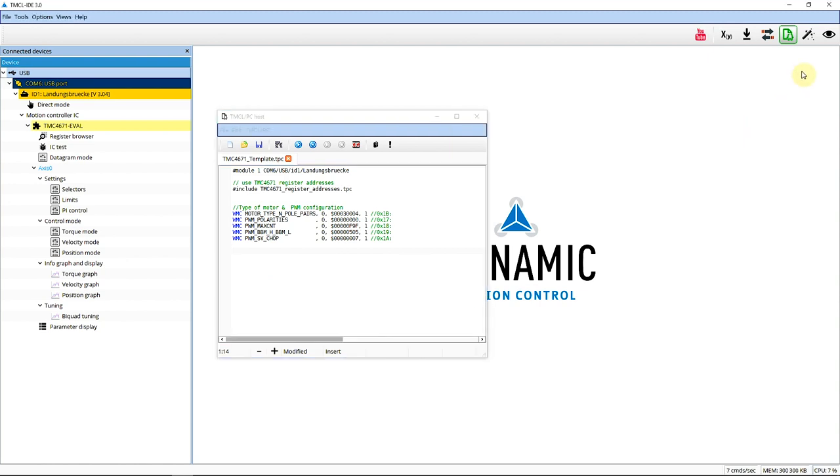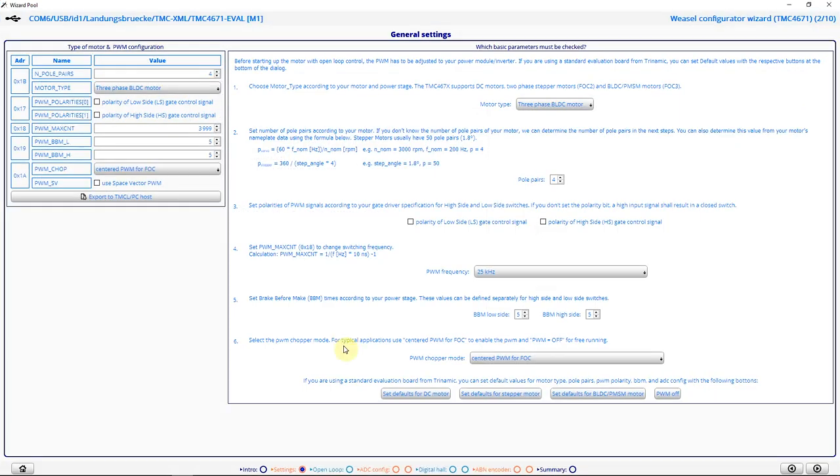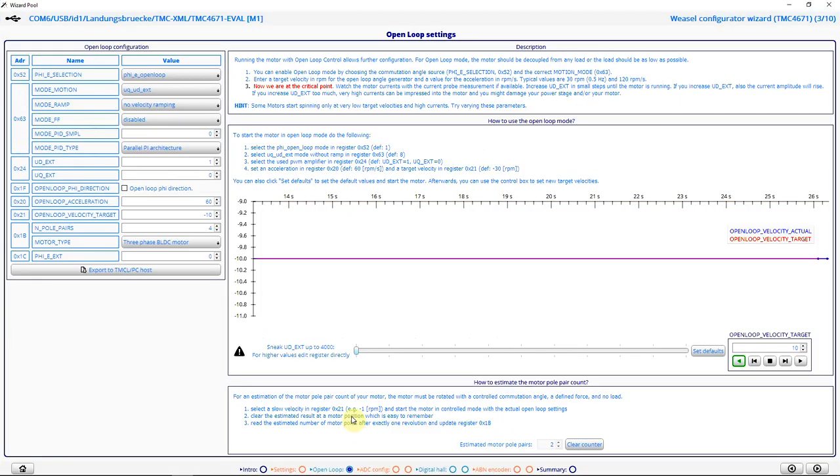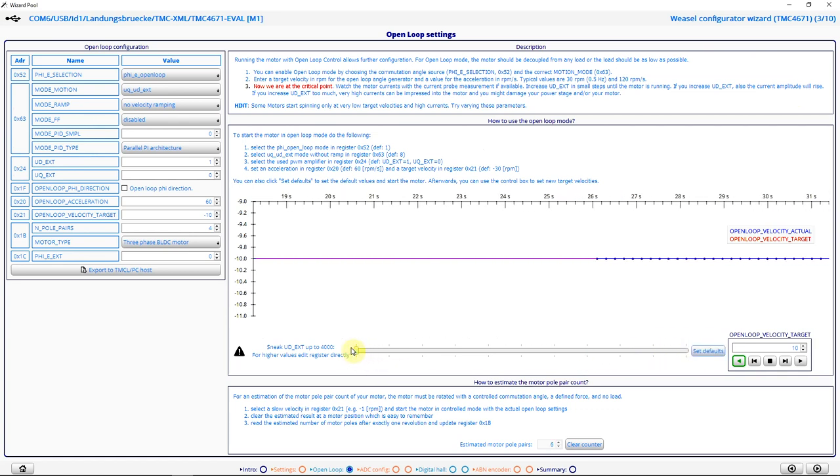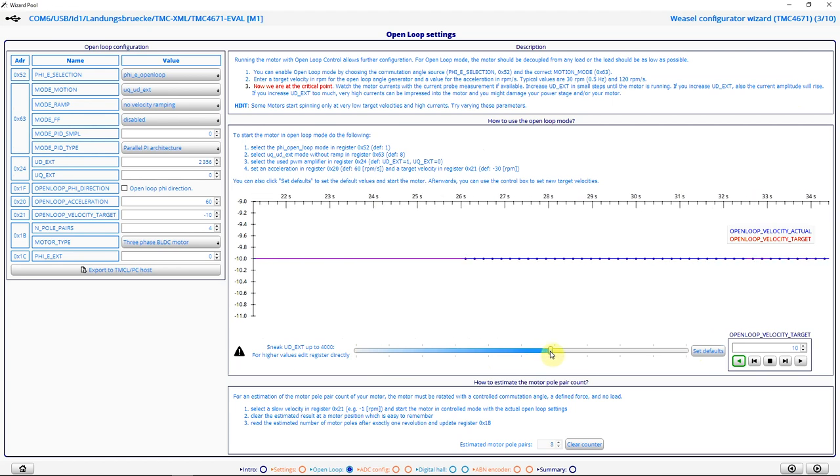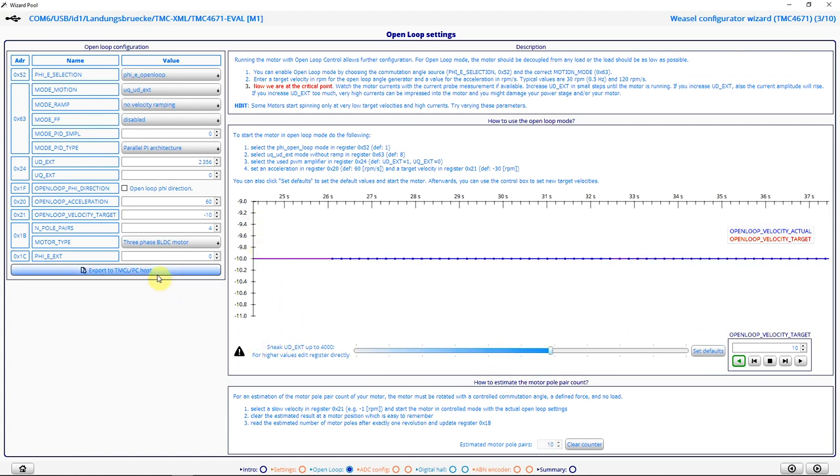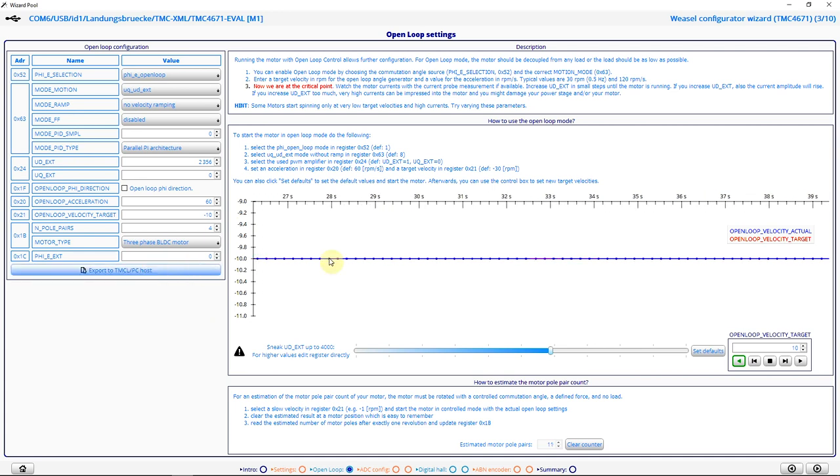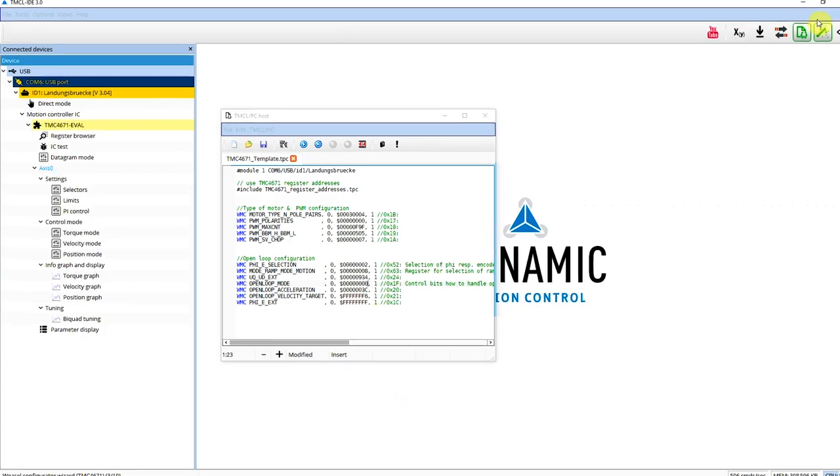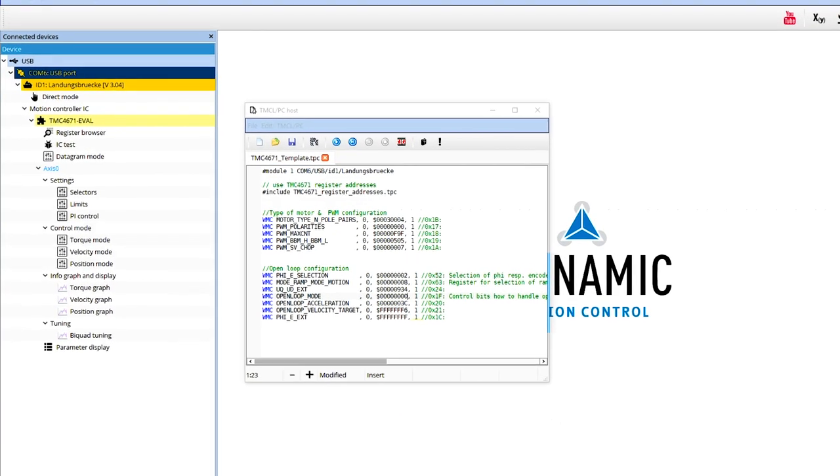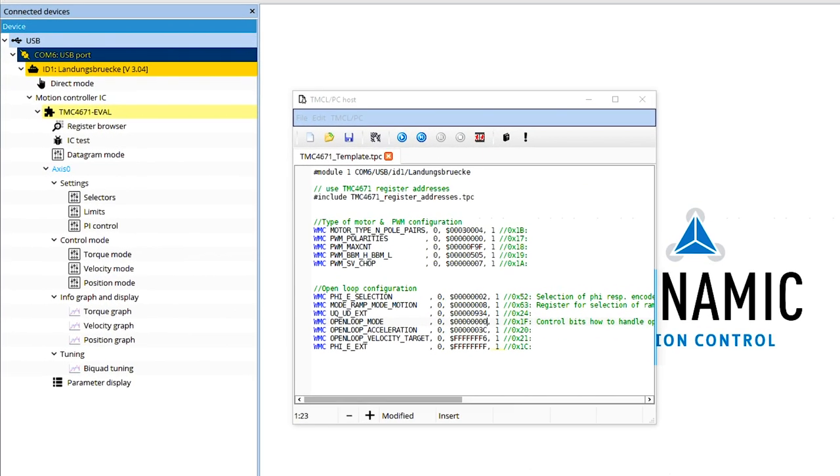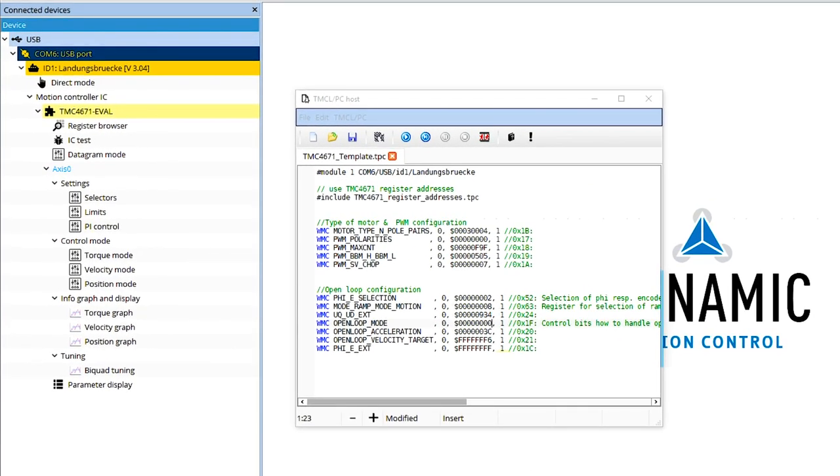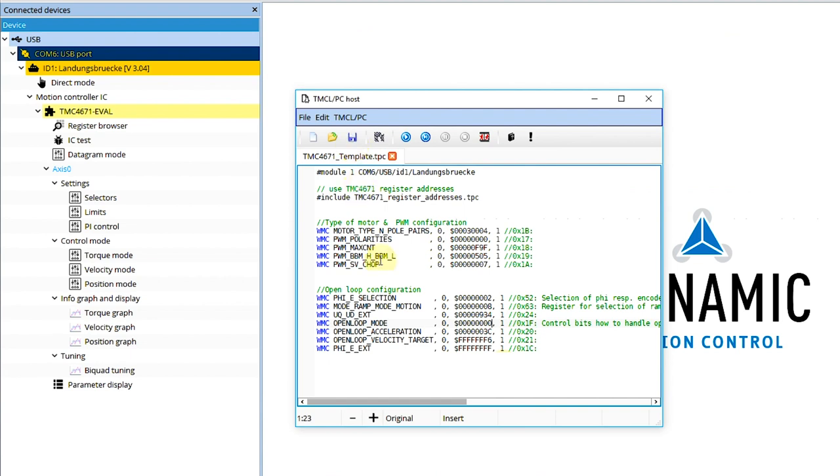So I can proceed with this for all other dialogs and generate a full configuration file. So I open the wizard again. I switch to open loop settings. I click set defaults. And I ramp up the voltage. So the motor turns again. And I click on export to TMCL PC host. I close the wizard again. And now I see my open loop settings here. Now I save the template.